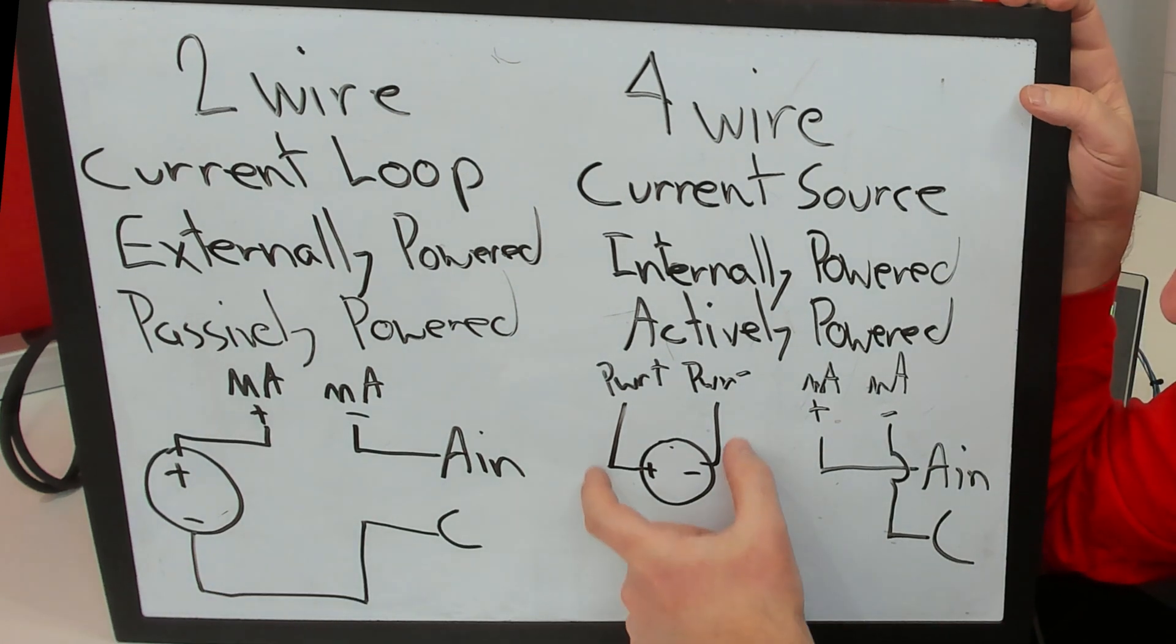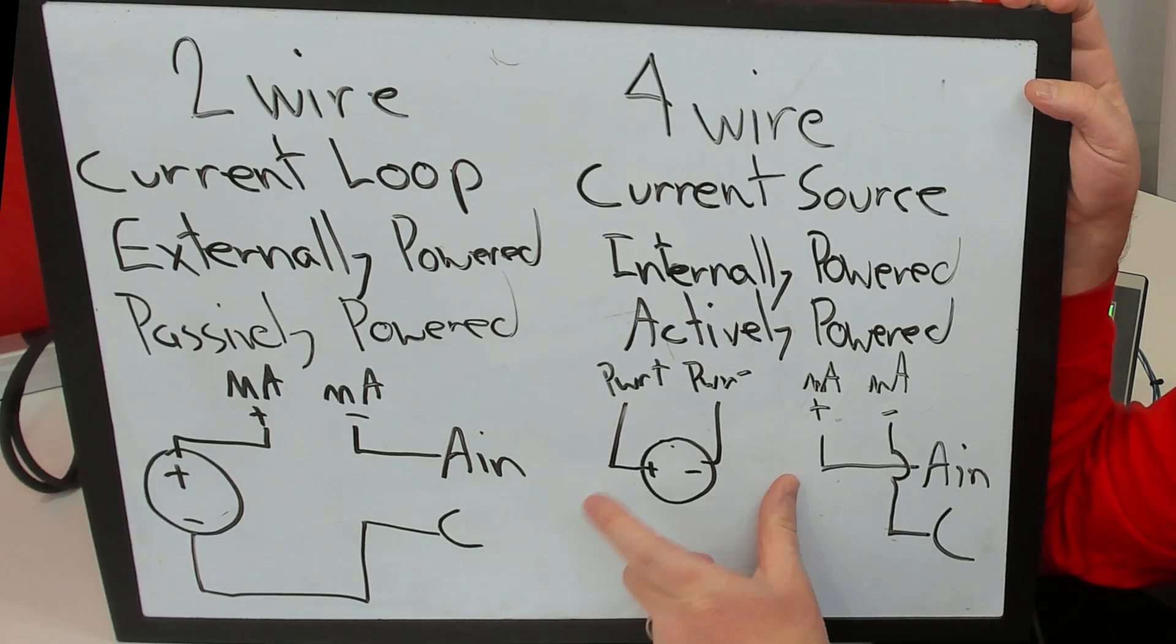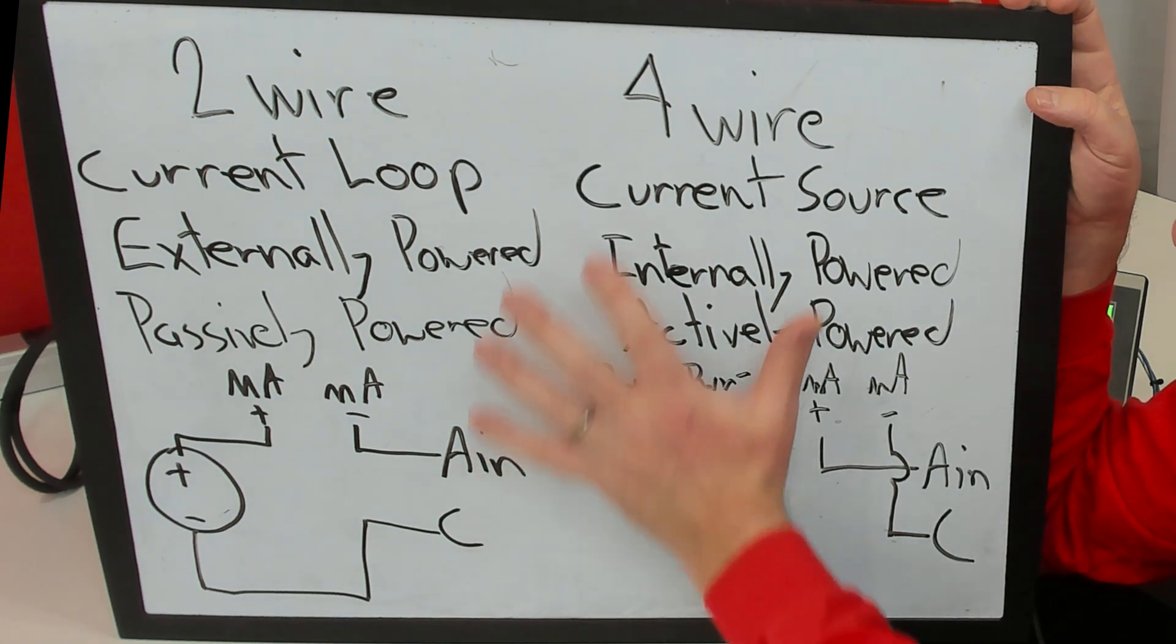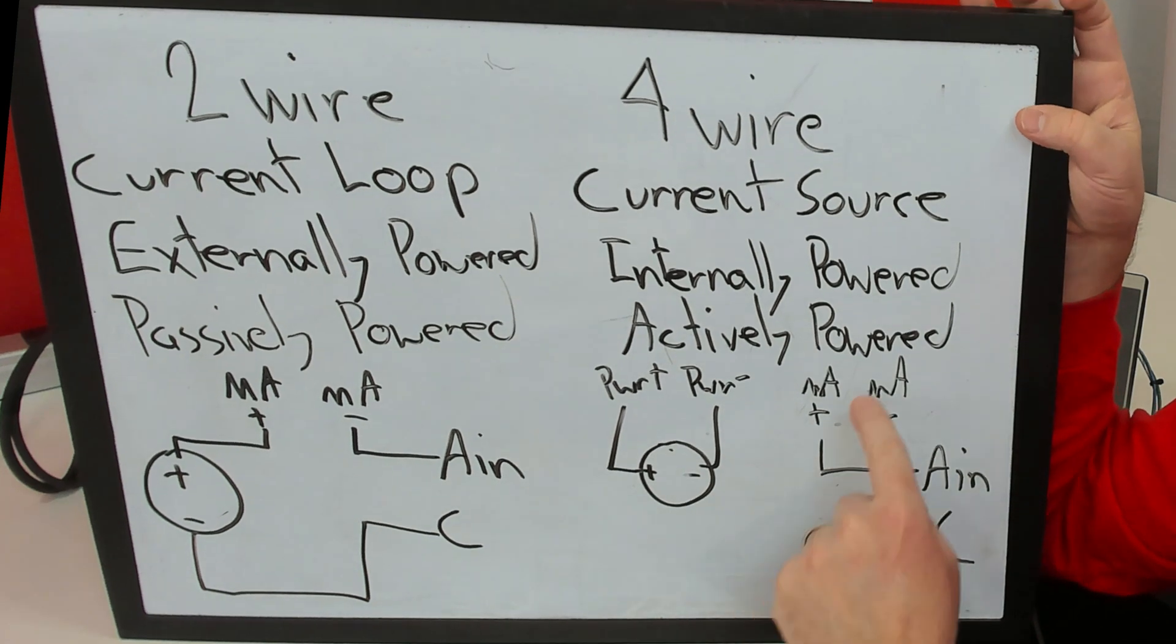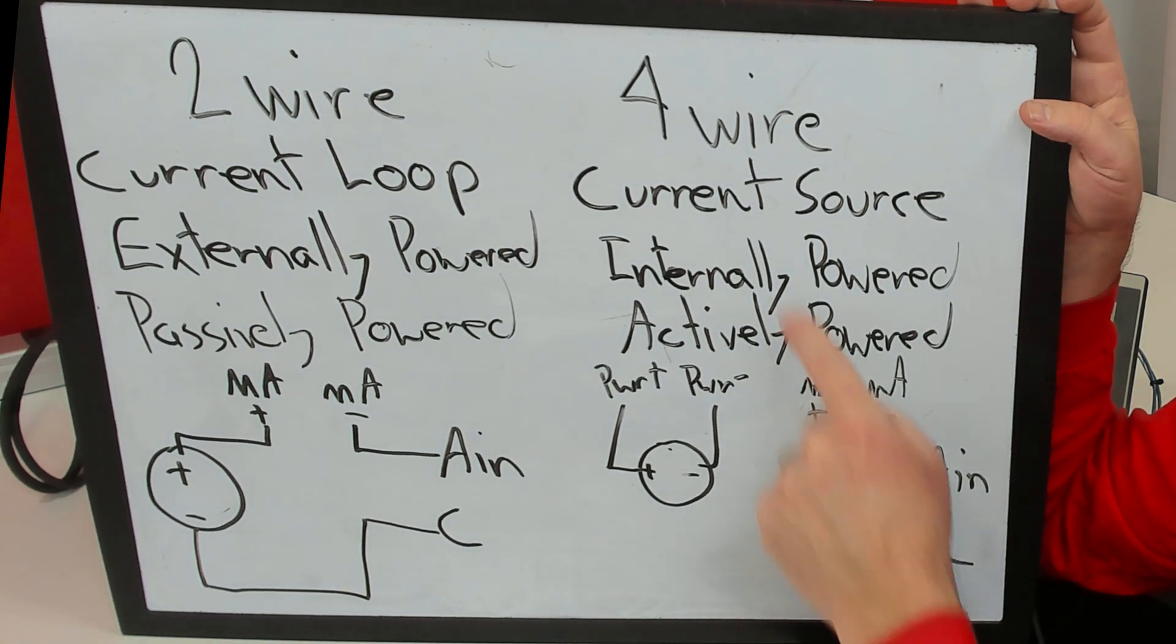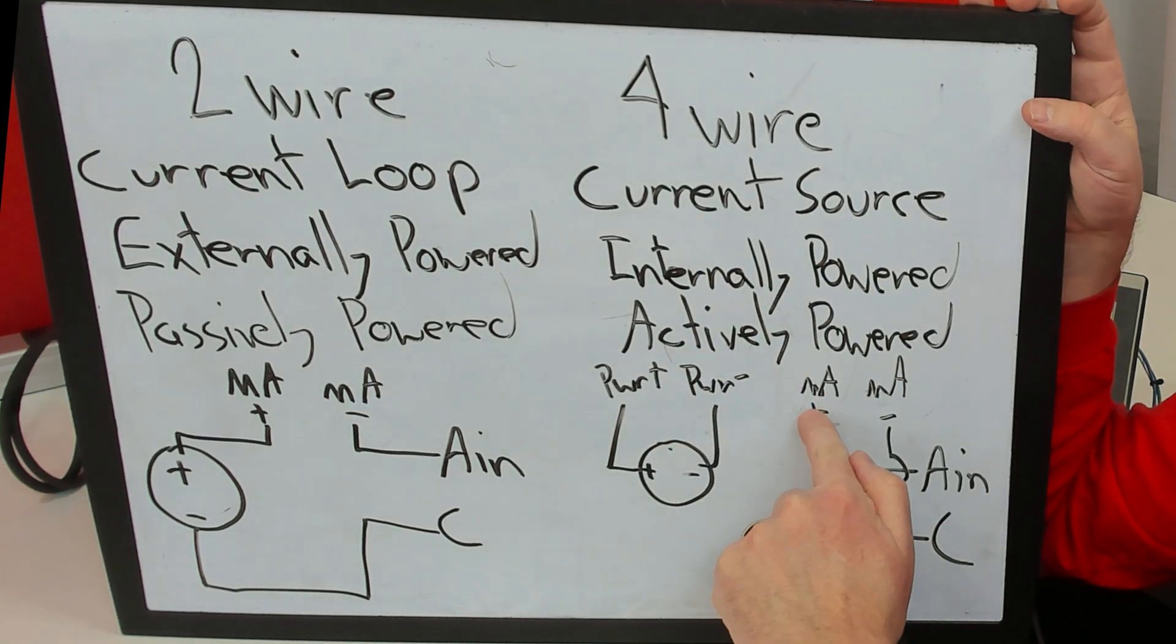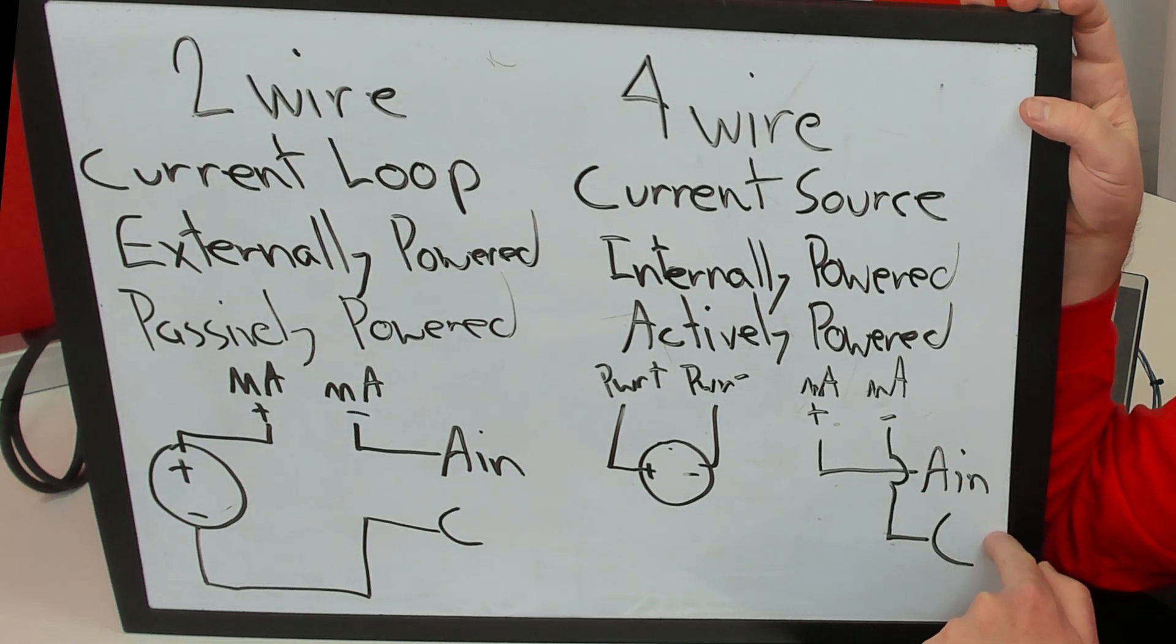Now if it's a four-wire device, it's going to be internally powered. It could be 24 volt DC powered, 24 volt AC powered, solar powered, 12,000 volt power, but mainly it's powered somehow somewhere else. And it's going to generate the entire loop or be the current source. And in this case, the positive milliamp will go to the analog in and the minus milliamp will go to the common.